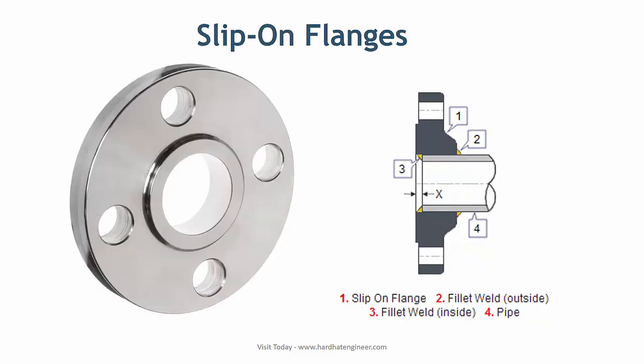Slip-on flange has a hole with a matching outside diameter of the pipe, through which the pipe can pass. The flange is placed on the pipe and fillet welded from both inside and outside. Slip-on flange is suitable for low pressure and temperature applications. This type of flange is available in large sizes also, to connect big bore piping with storage tank nozzles or any equipment nozzle.